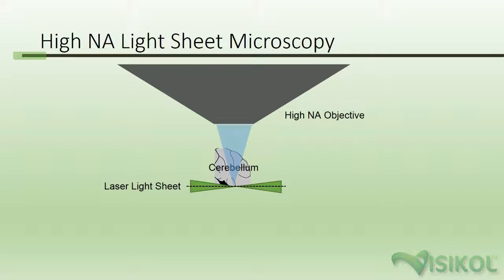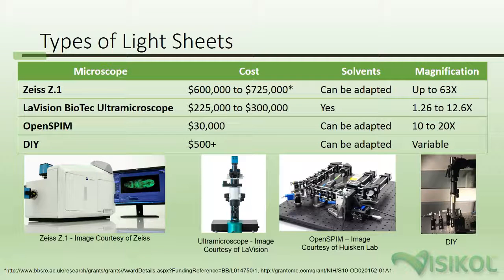The resolution of light sheet imaging can be improved by using higher numerical aperture objectives. However, improving the resolution of imaging by a factor of 2 will result in 8 times slower scans and 8 times more information being acquired from tissues. For very small regions of interest and higher resolutions, we would suggest using confocal microscopy instead.